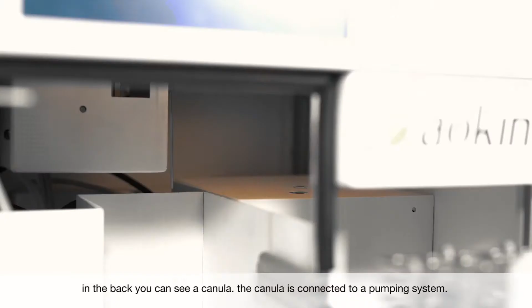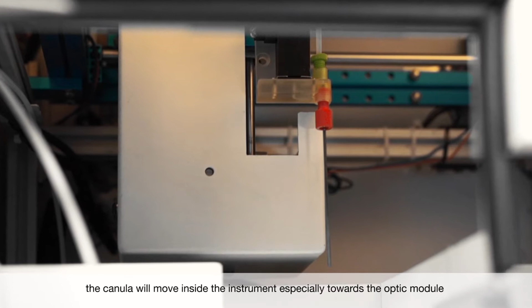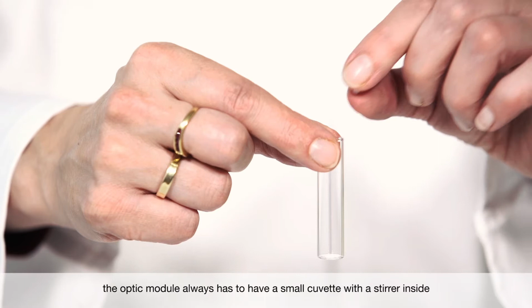In the back you see a cannula. The cannula is connected to a pumping system. The cannula will move inside the instrument, especially towards the optic module. The optic module always has to have a small cuvette with a stirrer inside. Make sure that the cuvette is pushed down and sits very firmly.